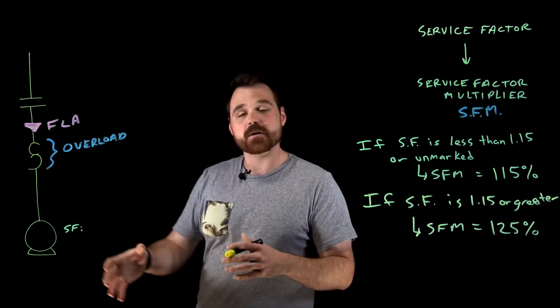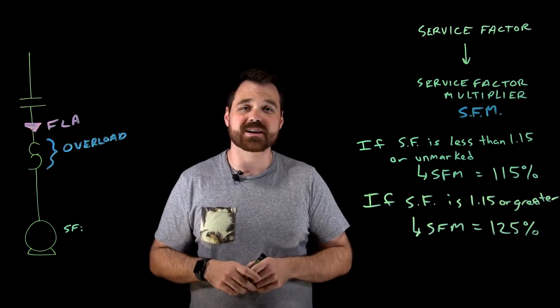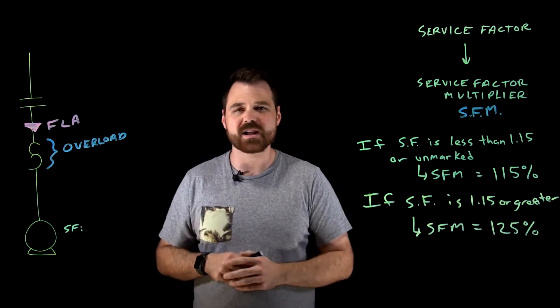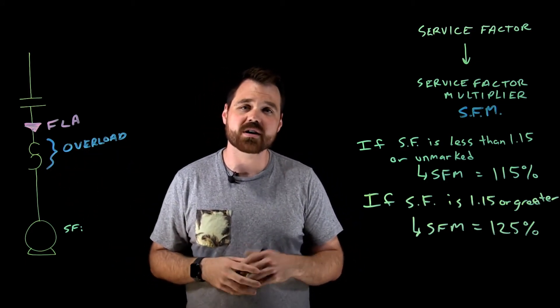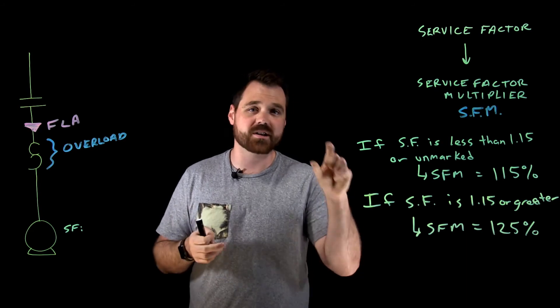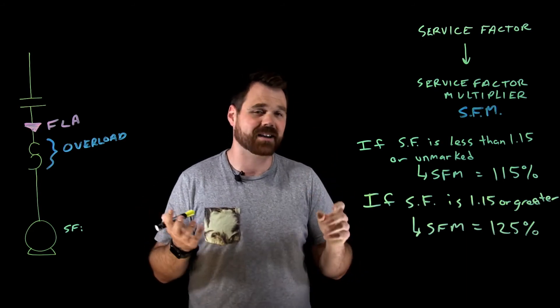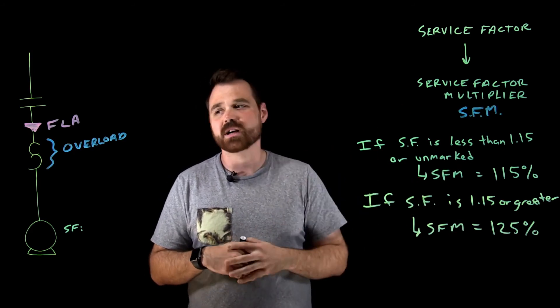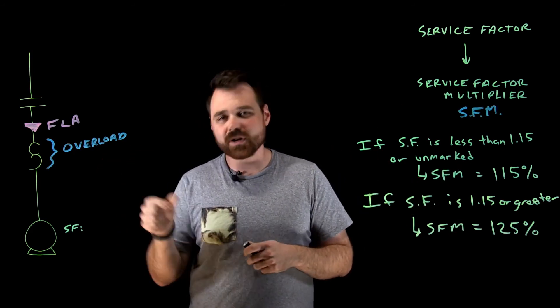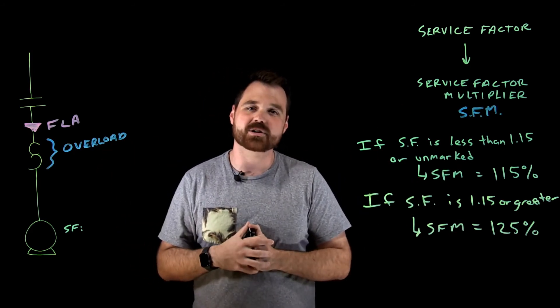And that's for a standard motor. And that's really important to remember sizing these overload conditions or overload devices. Quite often, it'll be a little set screw or a dial on the actual motor starter. Sometimes you'll be going to the wholesaler and you'll be buying heaters. If you're buying heaters, you cannot exceed the value you calculated, you have to go down. If you're setting the little screw, you just set it to exactly what your setting should be.